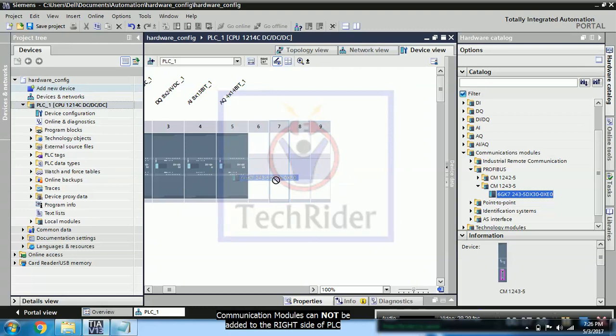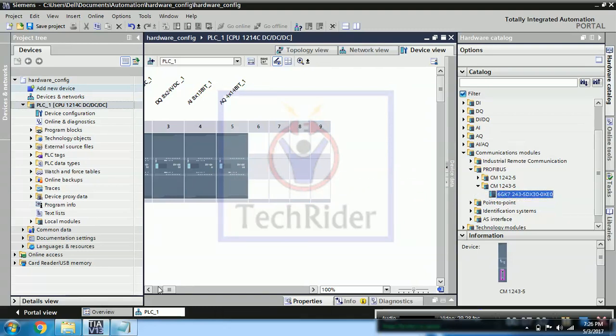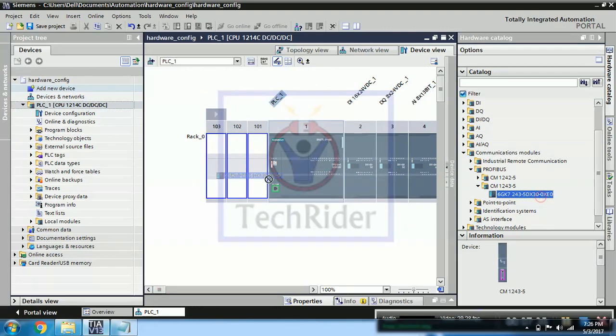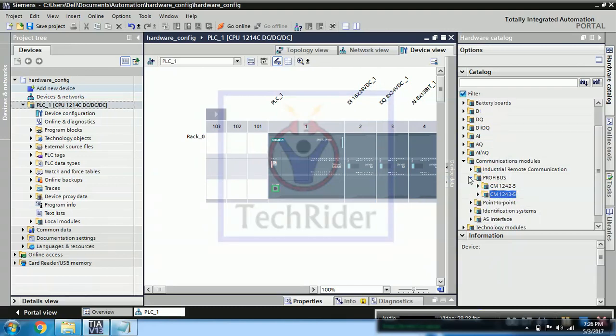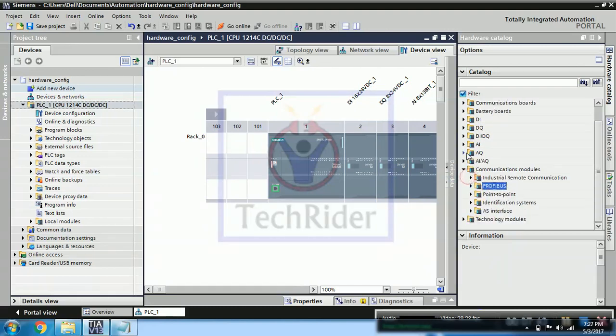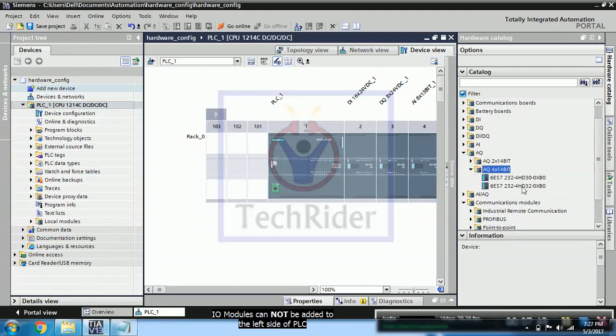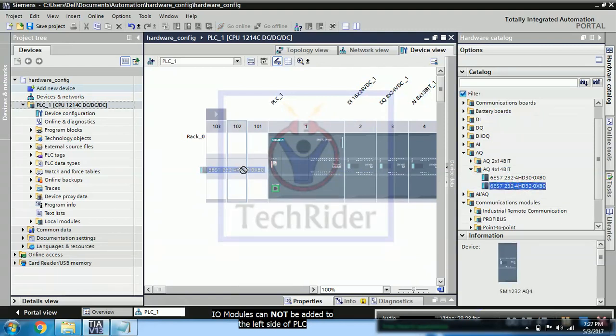But this is for your information. And you cannot add communication cards, Profibus communication cards, into IO cards and vice versa. You cannot add IO cards into communication card slots. So communication cards must be added to the left side of the PLC while IO should be added to right side of the PLC.